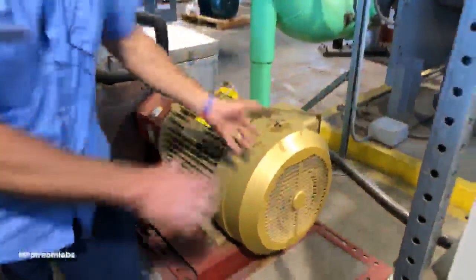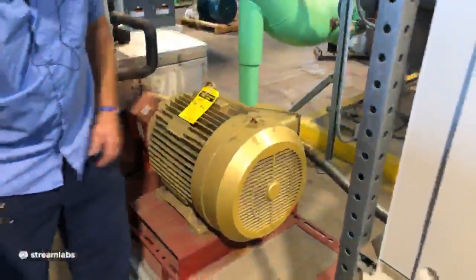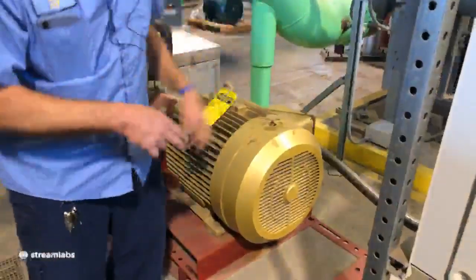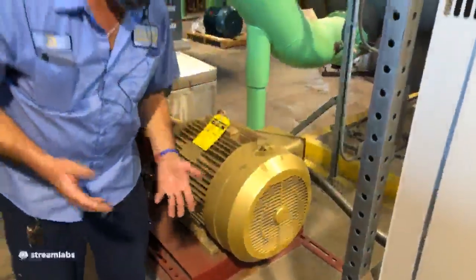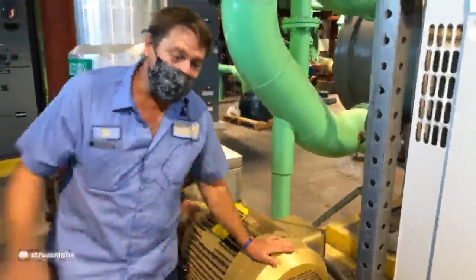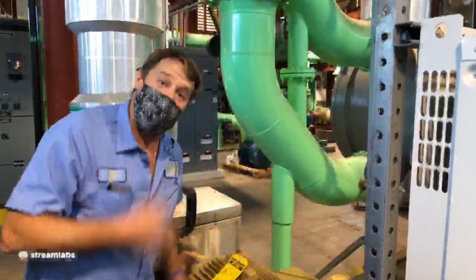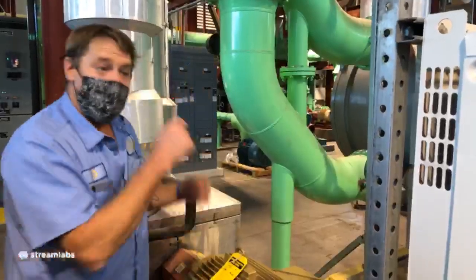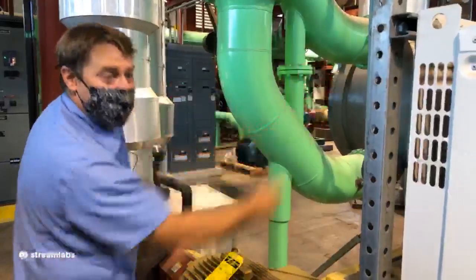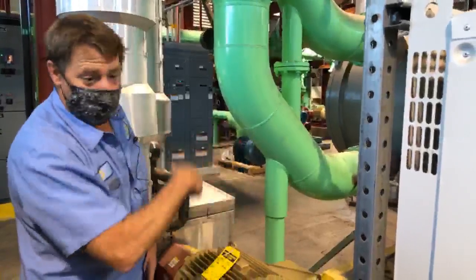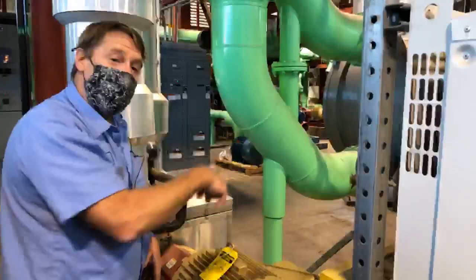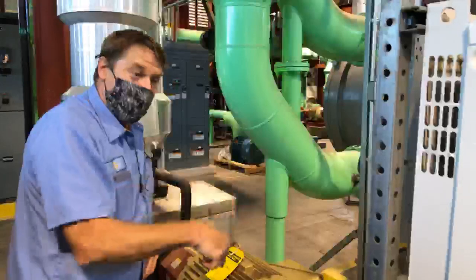All chillers have a primary pump. So the primary chill water pump is what pushes a predetermined amount of water through the chiller. And then the outlet from all the chillers goes to what we call a secondary chill water pump. So primary chill water pump pushes water through the chiller, and then the secondary chill water pump pushes water to the customer.